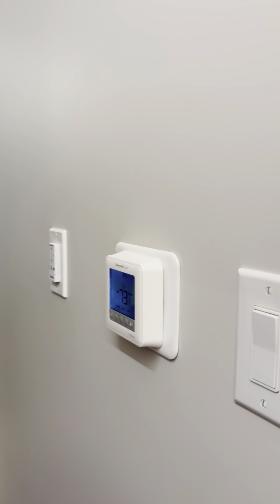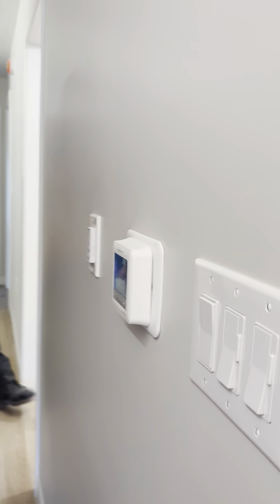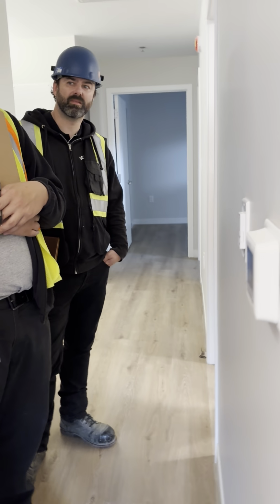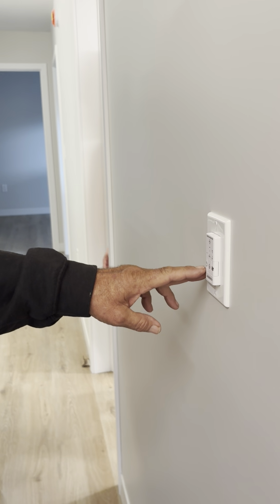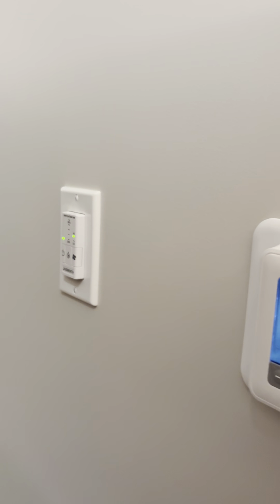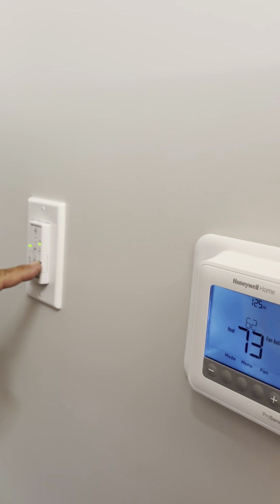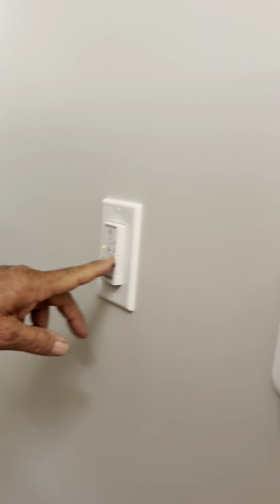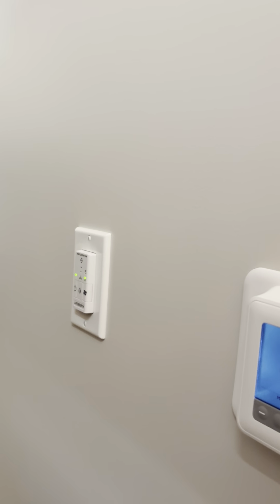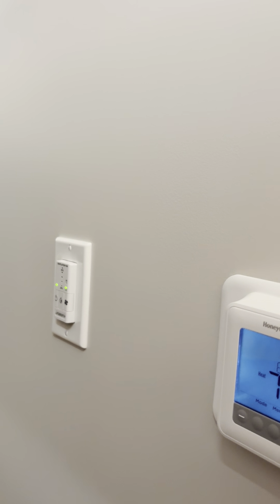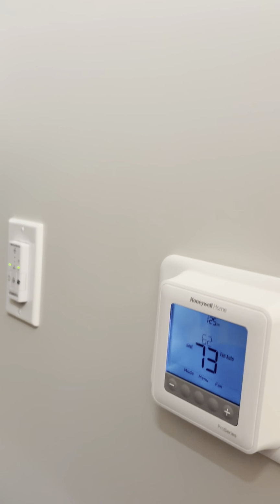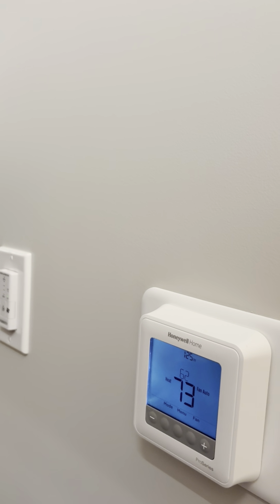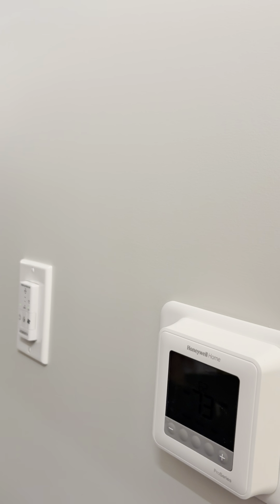So if you get a complaint that someone's fan never shuts off, check if the thermostat's been turned on continuously. What it should be set to is low speed. That way it controls at low speed all the time, which has been air balanced to supply the right amount of air needed for that space. So it's all been balanced.